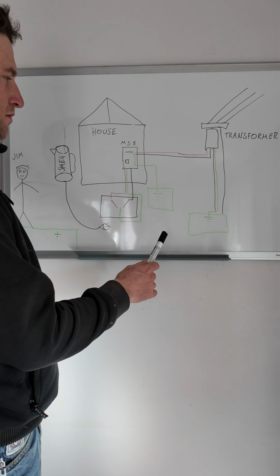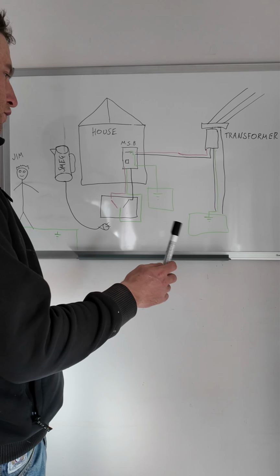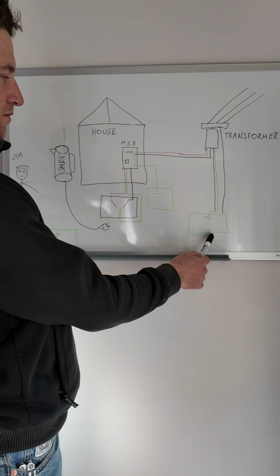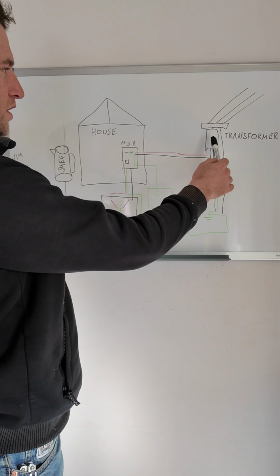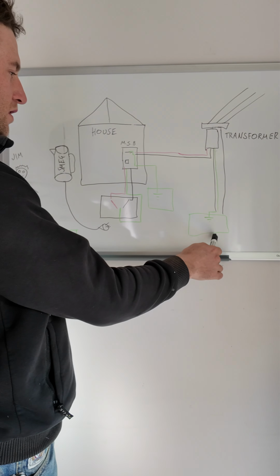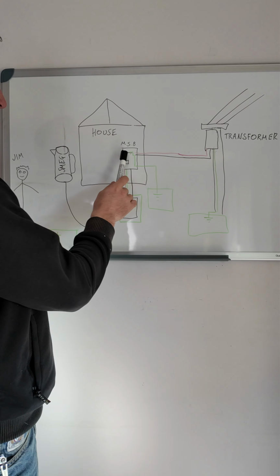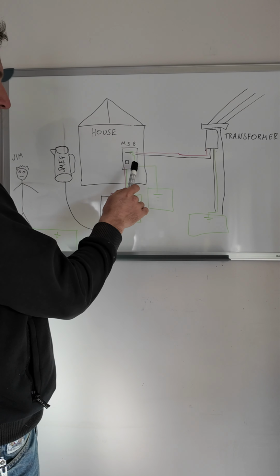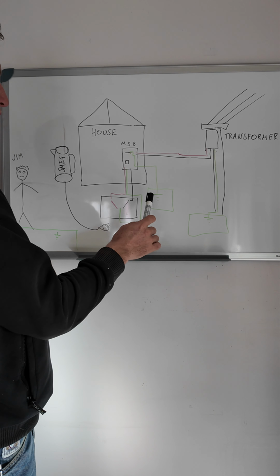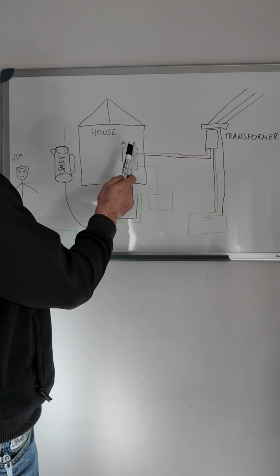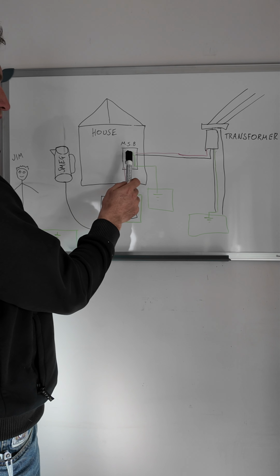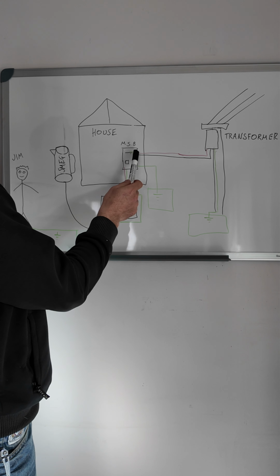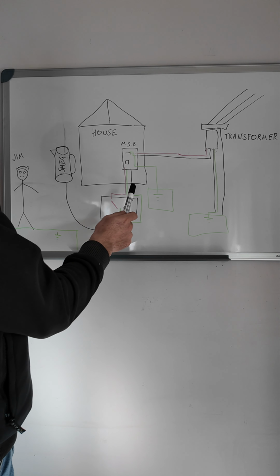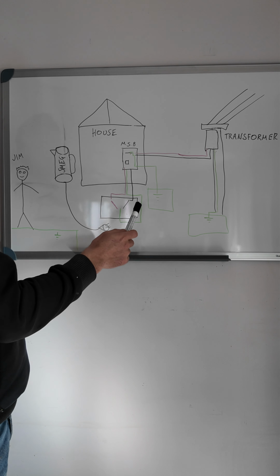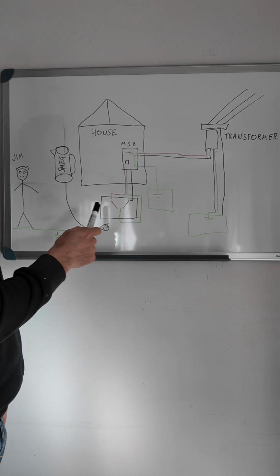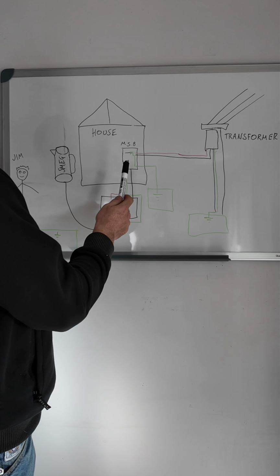Your earthing system is essentially made up of four different parts. You've got your pole earth, which comes from the transformer down the pole and into the ground. Then you've got your main switchboard main earth, which is for your main switchboard. Then you have your MEN link, which goes between your main neutral and your main earth. And then you have your circuit earths, which go along with each one of your circuits.